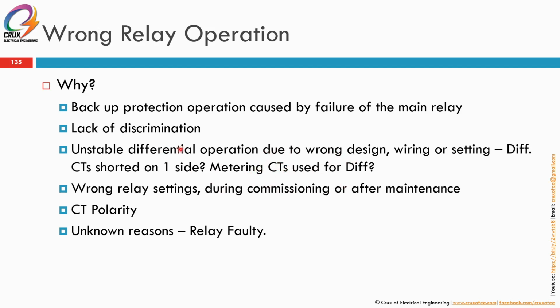Or it could also be the differential protection triggered due to wrong design or wrong wiring. Wrong wiring means you could reverse the S1, S2 termination. It means one side is looking into the equipment, the other side is looking out of the equipment. By right, for the differential CTs in the zone, both CTs must look into the equipment, facing the same direction. It can also be due to CT shorted on one side. If you do relay calibration or are commissioning, and you forget to open the CT secondary shorting link, it remains shorted. The upper side is open and reads current, the lower side is shorted and doesn't read any current.